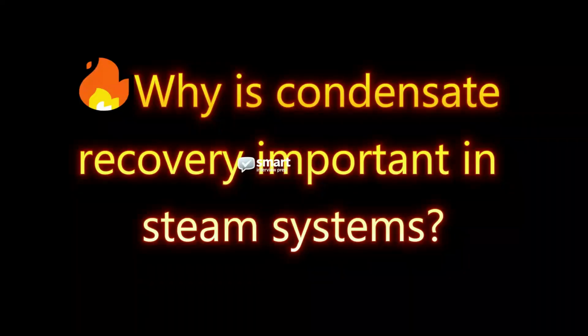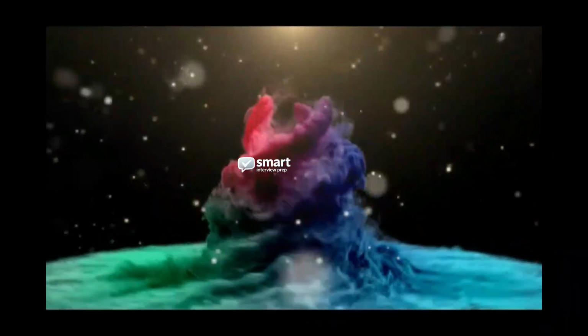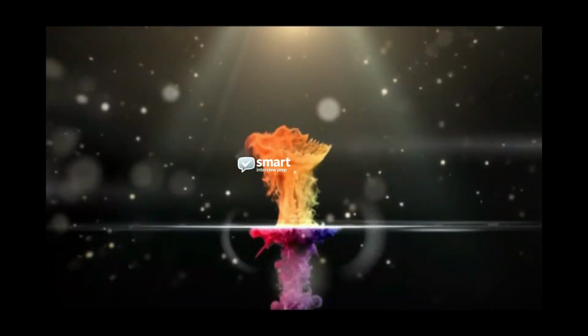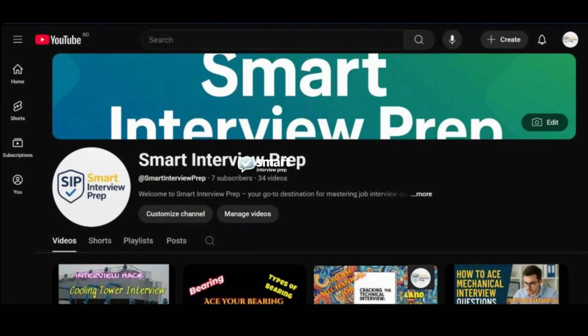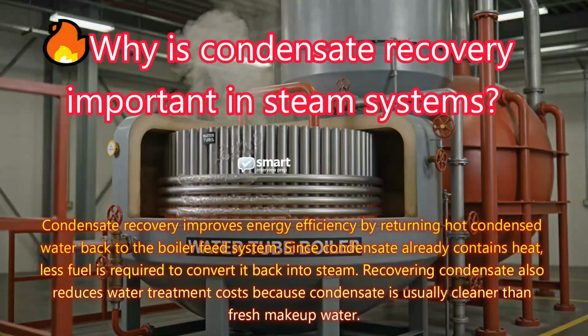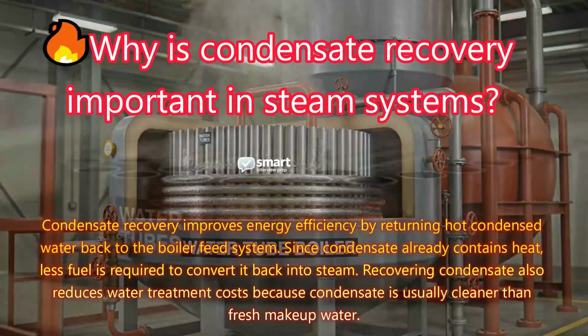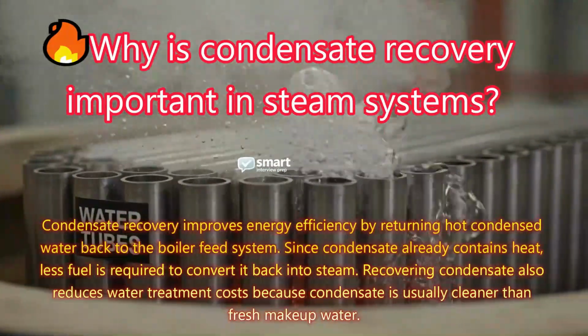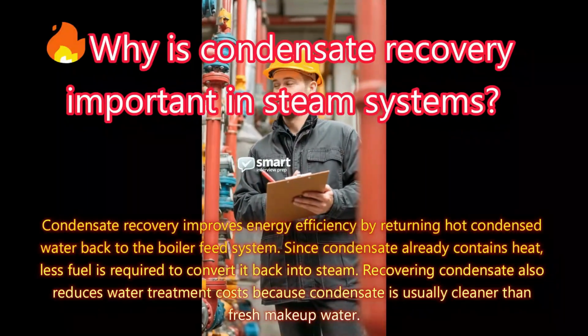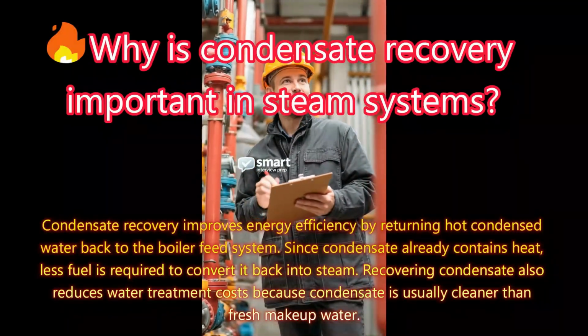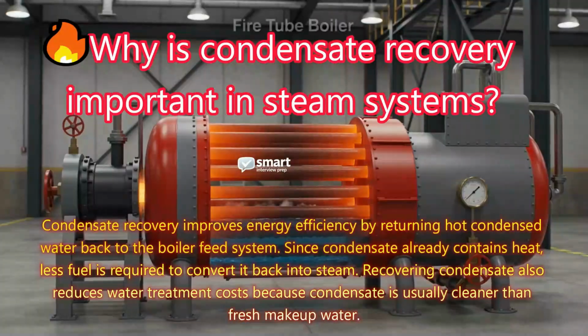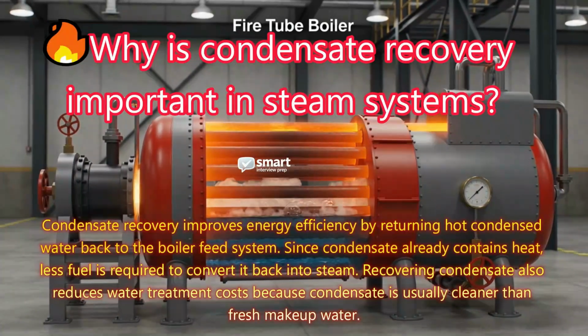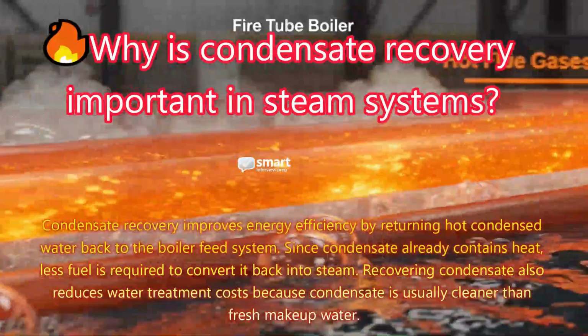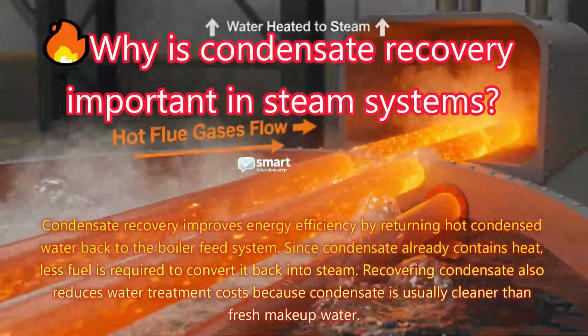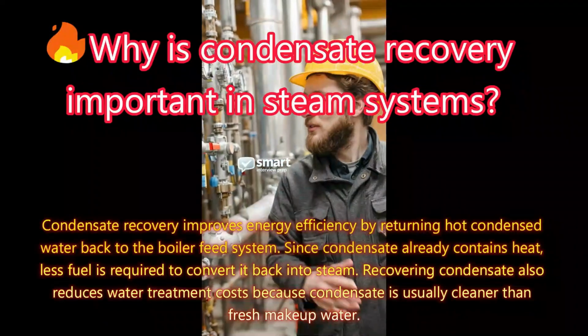Why is condensate recovery important in steam systems? Answer. Condensate recovery improves energy efficiency by returning hot condensed water back to the boiler feed system. Since condensate already contains heat, less fuel is required to convert it back into steam. Recovering condensate also reduces water treatment costs because condensate is usually cleaner than fresh makeup.